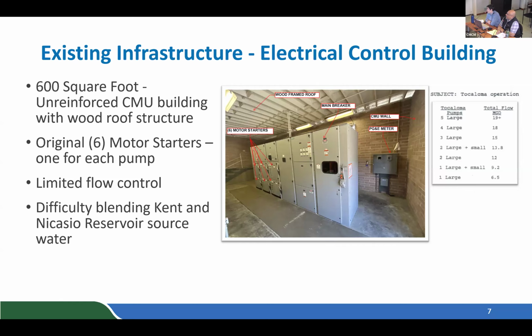The VFDs are more akin to what you would consider like a dimmer switch. So you actually have the ability to slowly turn on the pumps, which reduces your electrical demand charges. And you could also reduce the speed of your motors, which reduces the speeds of the pumps, and you could actually dial in flow. At the time in 1961, this was state-of-the-art technology. Fast forwarding 65 years, what we're looking to do is to put it in modern times with our VFDs. And because you cannot control the speed of the pump, you have limited flow control.